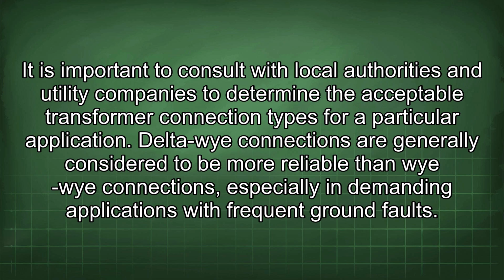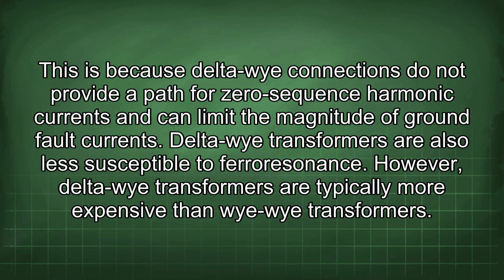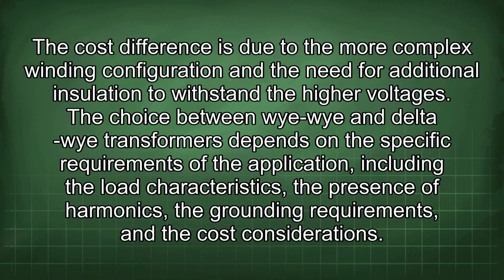Delta-wye connections are generally considered to be more reliable than Wye-Wye connections, especially in demanding applications with frequent ground faults. This is because delta-wye connections do not provide a path for zero-sequence harmonic currents and can limit the magnitude of ground fault currents. Delta-wye transformers are also less susceptible to ferroresonance. However, delta-wye transformers are typically more expensive than Wye-Wye transformers. The cost difference is due to the more complex winding configuration and the need for additional insulation to withstand the higher voltages.